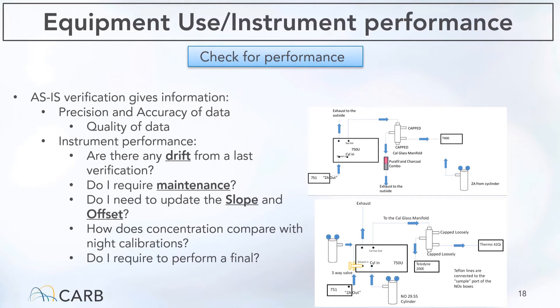As calibrators, we have the opportunity to analyze the performance, precision, and accuracy of the particular analyzers that we are calibrating. We ask ourselves: has the concentration drifted from the last verification? Do I need to perform any maintenance? Do I need to update the slope or the offset of the analyzers? How do the concentration values compare to the night calibration? Or do I need to perform a final check after any maintenance or changes have been done? These are important questions to ask in regards to understanding instrument performance and comparing to previous data.